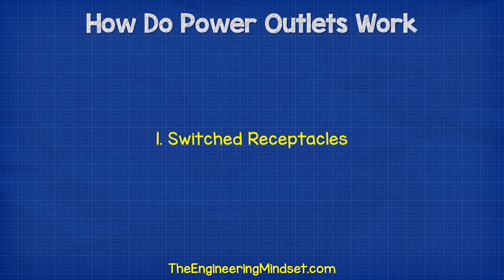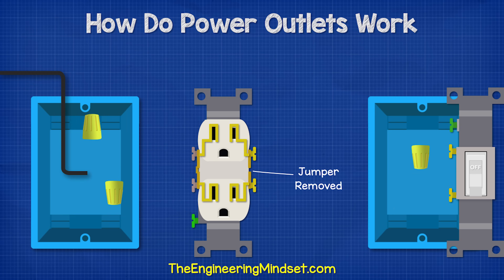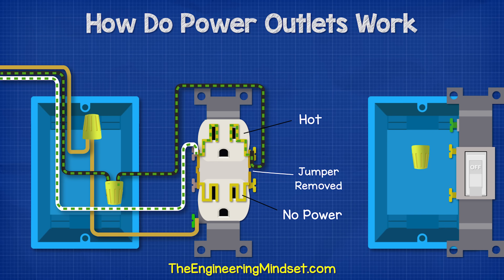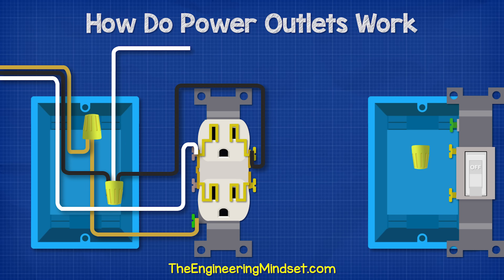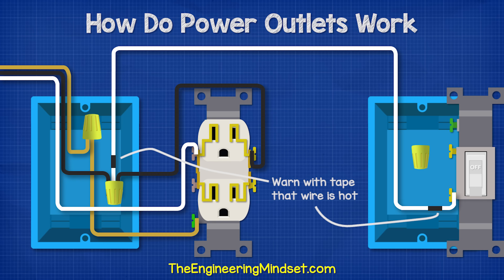One application is when using switched receptacles, like a circuit that allows half of the receptacle to remain hot while the other half is controlled by a switch. For this, we bring the hot wire in and connect this to the wire nut. We then run another hot wire from there over to the top hot terminal, and run our neutral wire back to the service panel. Of course, we need to also include our ground wires. We then run a white wire from the hot wire nut and take this over to the lower terminal of the switch, placing some tape on this wire to warn that it is hot.